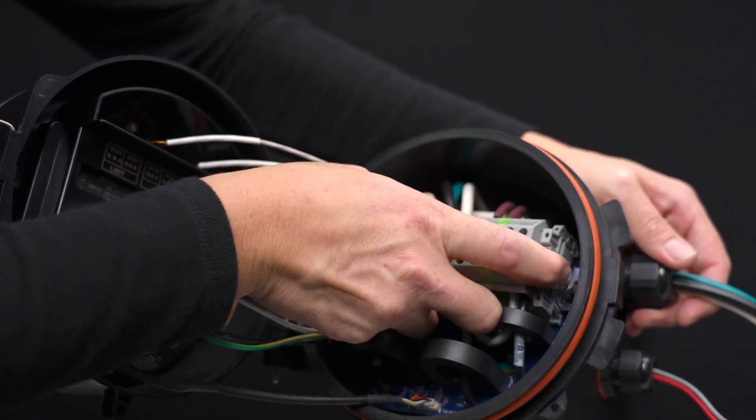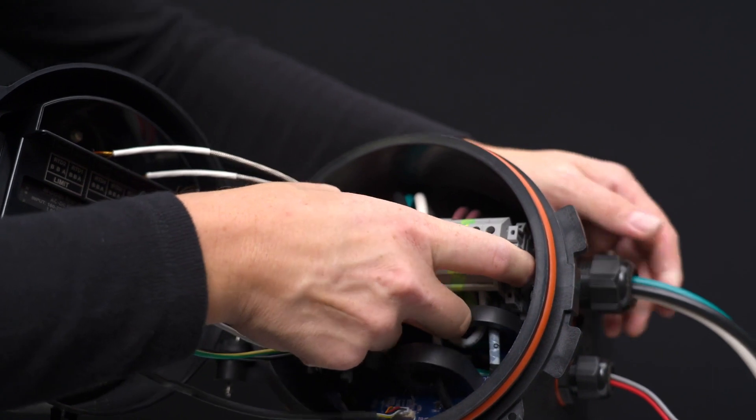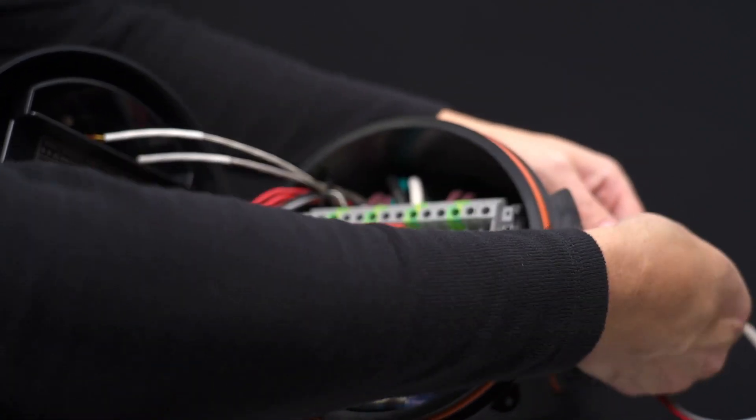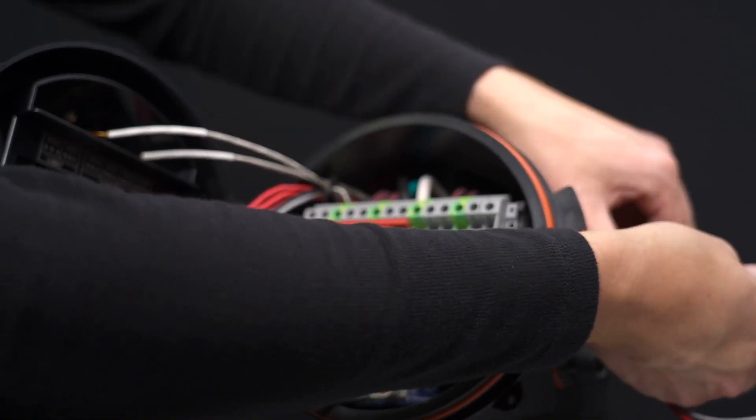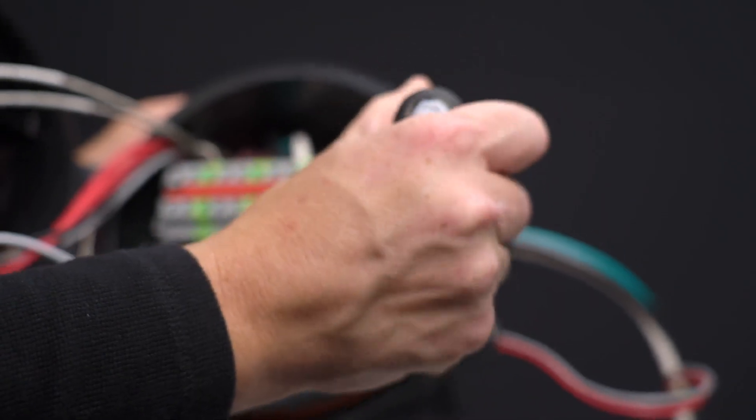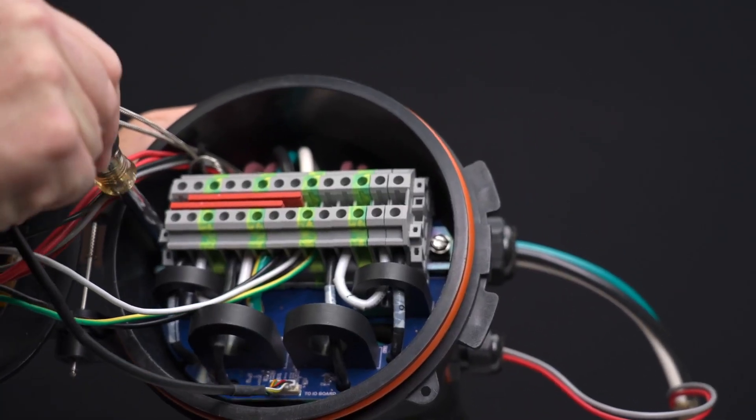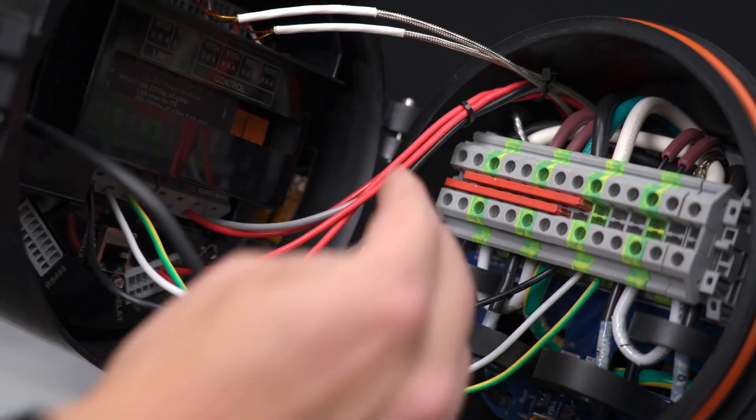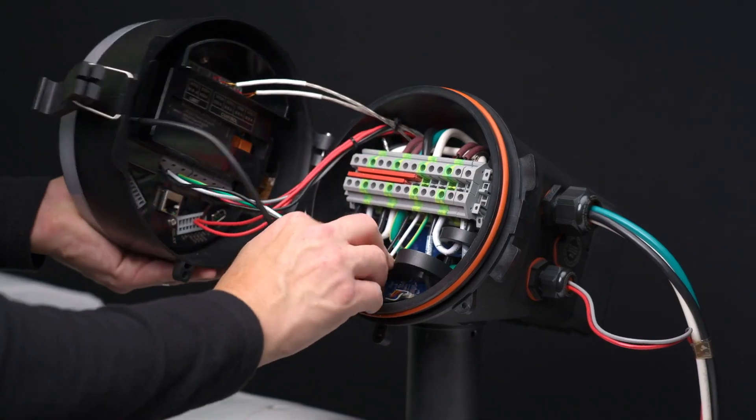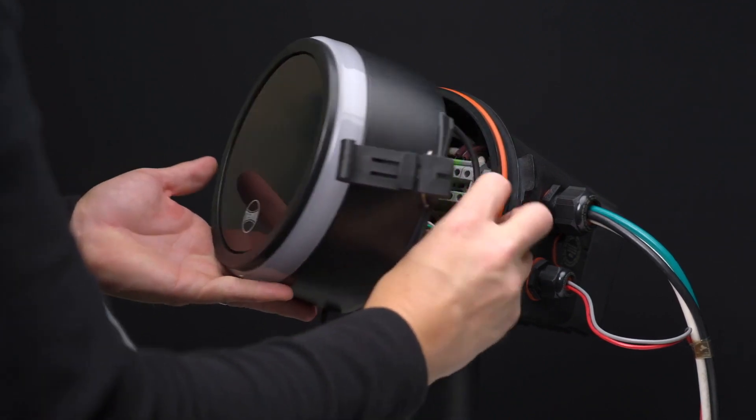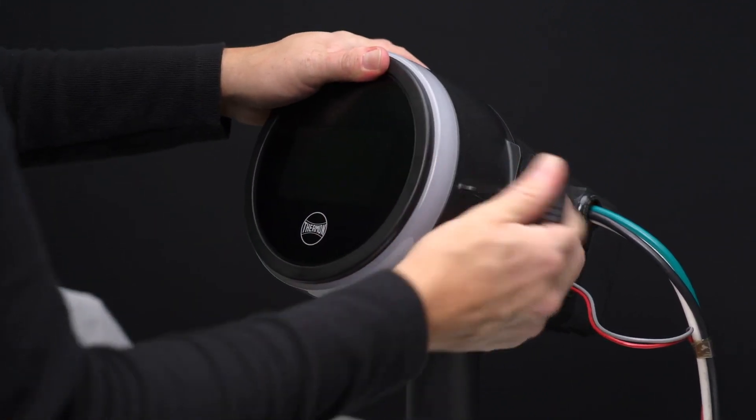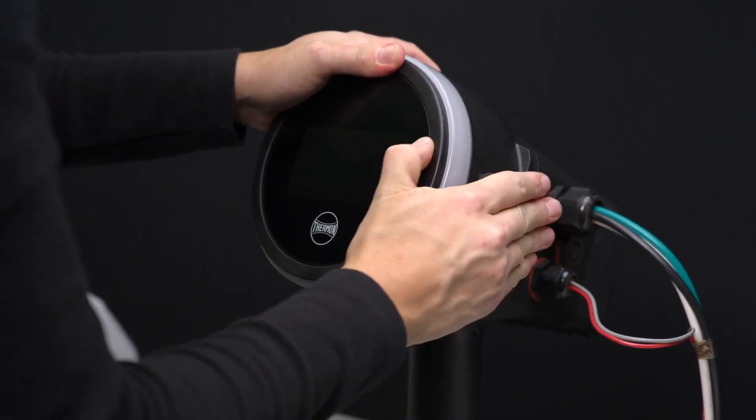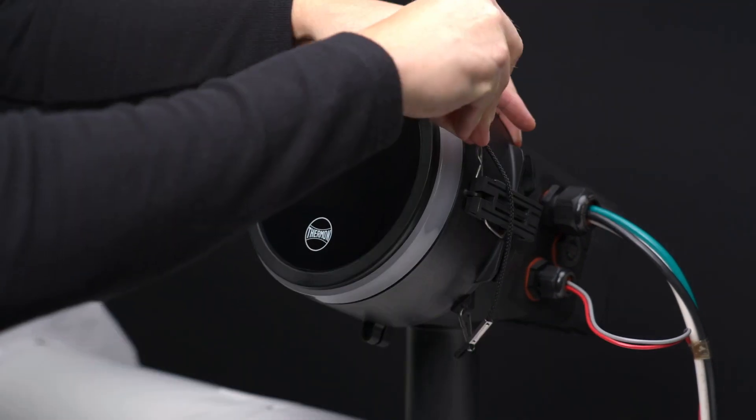With all wiring terminated, carefully place the current monitoring and termination assembly back in the housing. Tighten to 14 to 16 inch pounds. Lift the front end vertically to release from the locked position. With wires routed along the sides of the terminal blocks, carefully close the front clip, making sure not to pinch wires. Lock the latch and insert the pin.